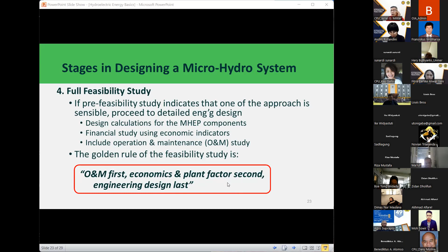So very briefly, let me discuss the plant factor and the load factor, as these are important factors in the design of the microhydro system. Plant factor, also called capacity factor, is the ratio between the actual energy used versus the actual energy available, while the load factor is the ratio between actual energy used versus the load connected.